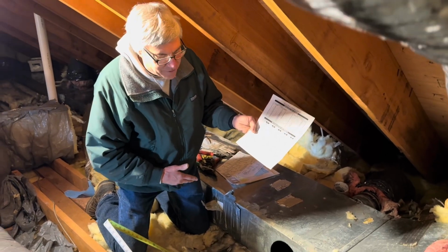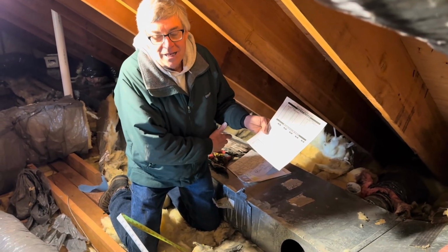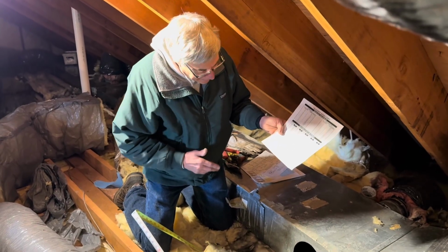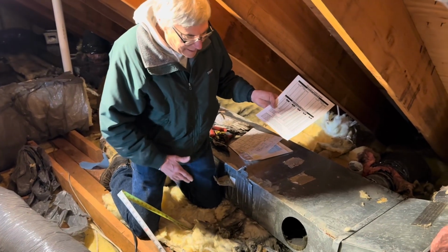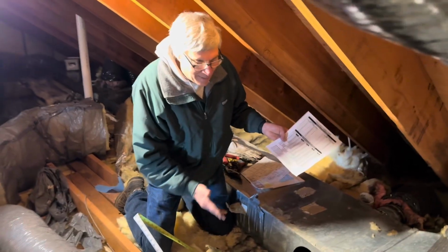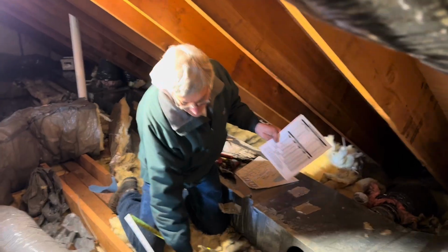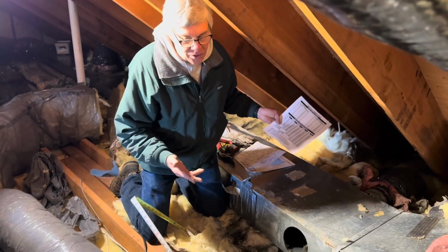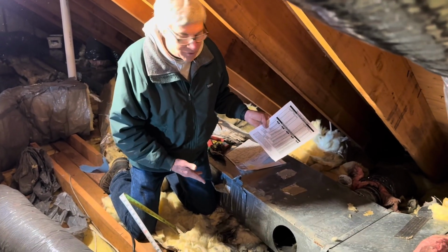One of them is you get a greater velocity of air because there's less resistance with an unlined duct. And number two, it has a greater capacity to carry more air. And then we would wrap the outside of the ducts with insulation, which this also was wrapped, but there are also some flaws in the way that was done.